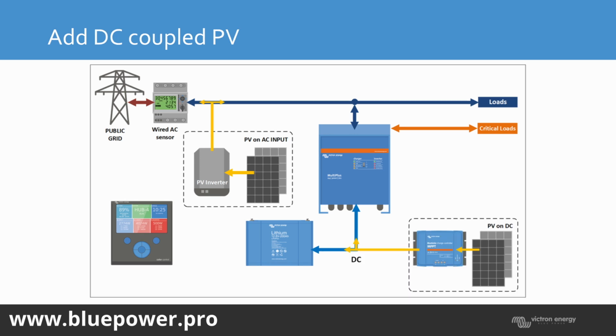Now we can add a DC coupled PV onto the system. So that's just a normal Victron DC MPPT that charges your battery. So what this does is it charges to the battery bank directly, and your loads will be then fed from the Victron inverter, which inverts the PV power to your loads.